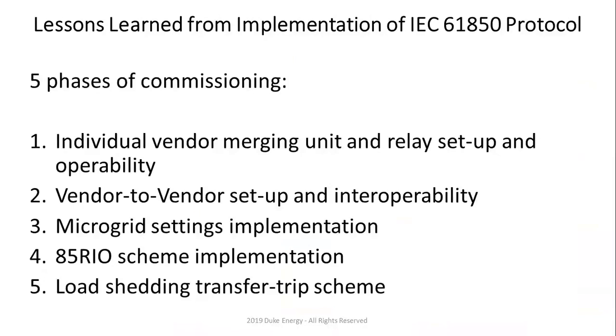When you have the 61850 protocol, as you probably know, you got 2 things. You got sampled values, which are CTs and PTs, and you got your GOOSE messages for status points, right? So everything in 61850 is a function of your communication network. So you have to understand how to build this communication network to make sure that it works. All right.